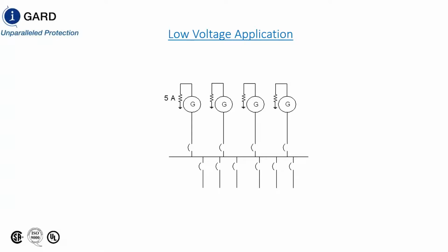Again, according to CSA and NEC, NFPA, if you limit the fault current to a low value in the NEC, and to 10 amps at less than 5 kV in CSA, then you don't have to trip and you have an arc flash mitigation technique. If you limit the fault current to 50 amps, you must trip.